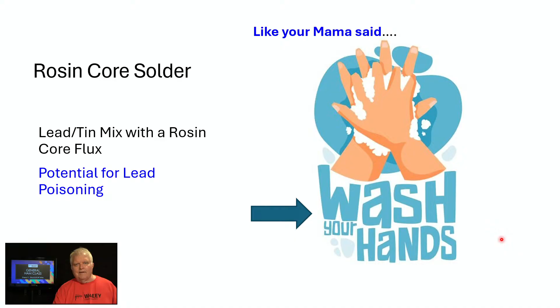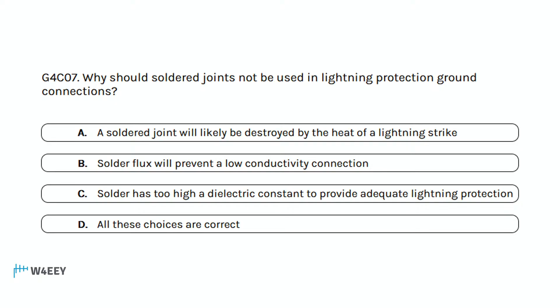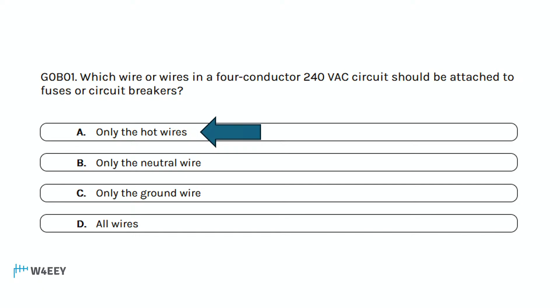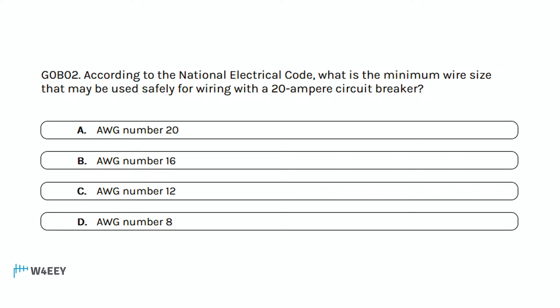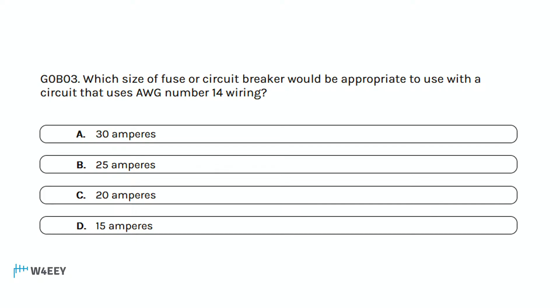All right, let's answer some questions, see how we're doing. So why should solder joints not be used in lightning protection ground connections? Yeah, a soldered joint will likely be destroyed by the heat of a lightning strike. And which wire or wires in a 4-conductor 240-volt AC circuit should be attached to fuses or circuit breakers? Yeah, only the hot wires, yes. And according to the National Electrical Code, what is the minimum wire size that may be used for wiring with a 20-amp circuit breaker? Charlie. Yep, number 12, American wire gauge number 12. And which size of fuse or circuit breaker would be appropriate to use with a circuit that uses AWG number 14? Delta. 15 amps. Great, you got it.